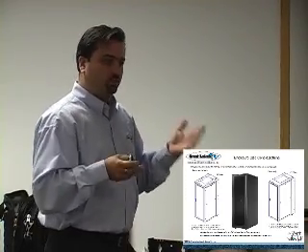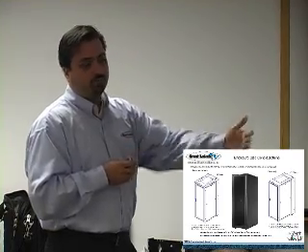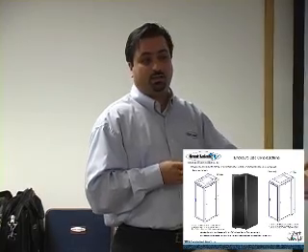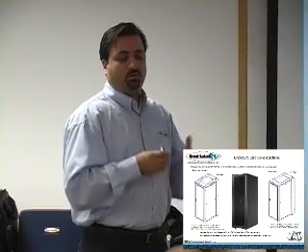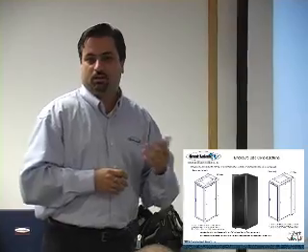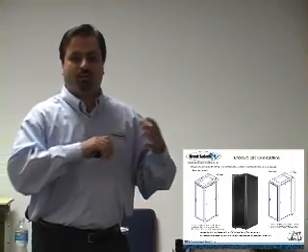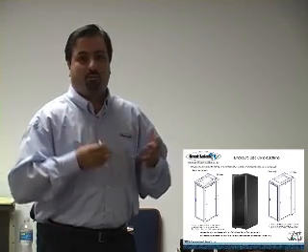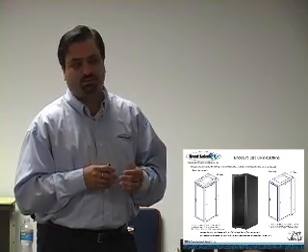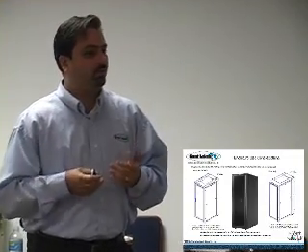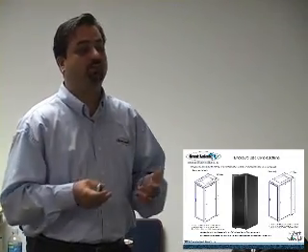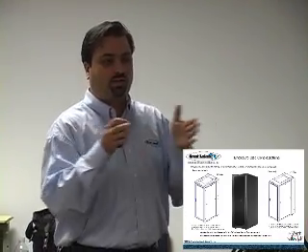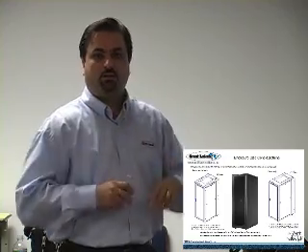So some people will always want to go with a 24 wide and go deeper. That's what we're seeing as a trend. We're seeing cabinets going 24 by 48, and what they're doing is putting 4 PDUs, 4 circuits, on one side of the cabinet and then managing all the cables on the other side. People are trying to still jam that amount of density into a 36-inch deep enclosure, and they're coming to us with heat issues. What happens is there's no way around it for this physical space. You have to go deeper and start putting everything on the outside to ease up that heat flow.